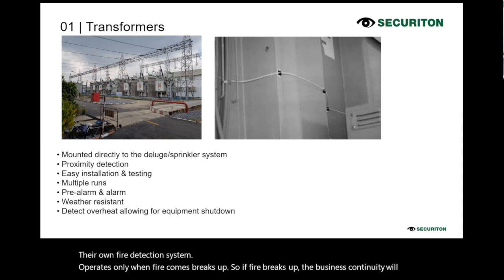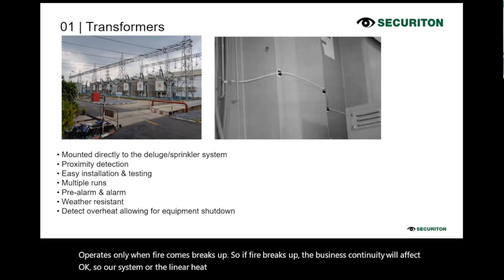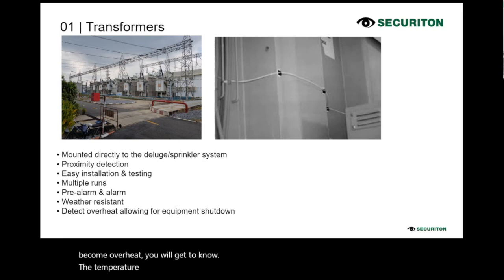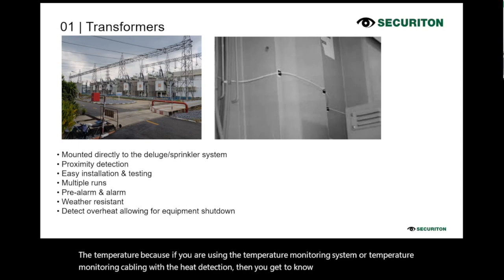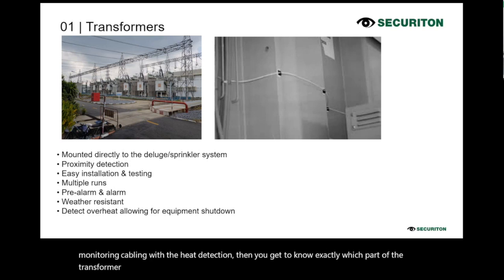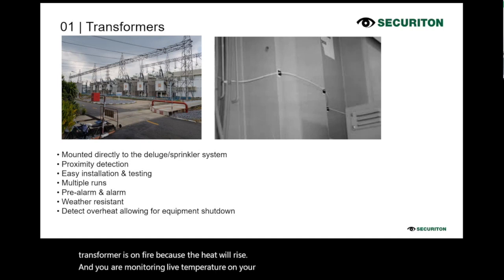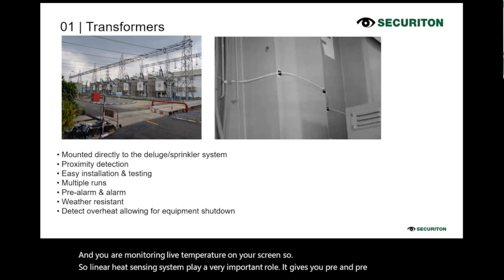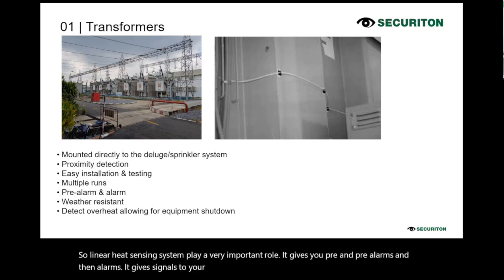Our system, the linear heat sensor, gives you a detection when the transformer starts to overheat. You will get to know the temperature, because if you are using the temperature monitoring system or temperature monitoring cabling with the heat detection, then you know exactly which part of the transformer is on fire, because the heat will rise and you are monitoring live temperature on your screen. So the linear heat sensing system plays a very important role. It gives you pre-alarms and then alarms. It gives signals to your fire brigade also, and to your third party system.